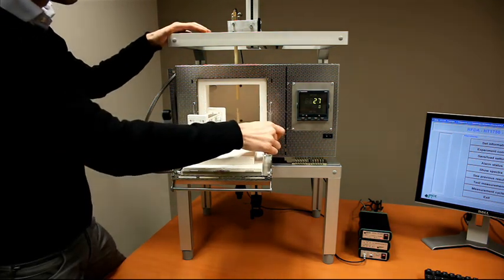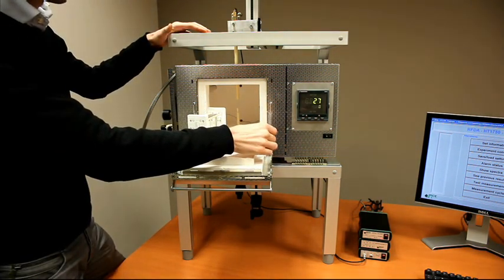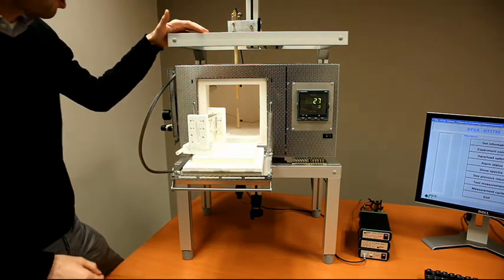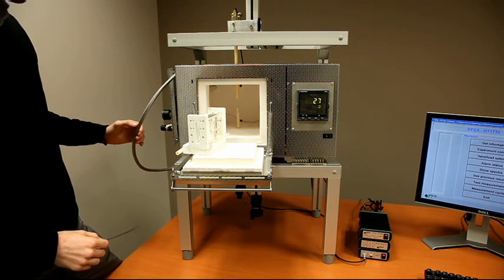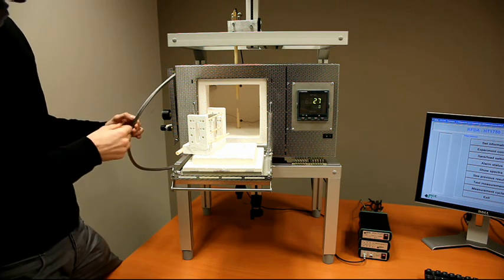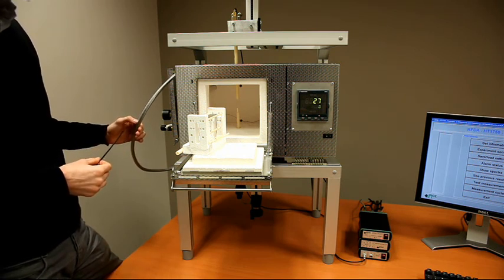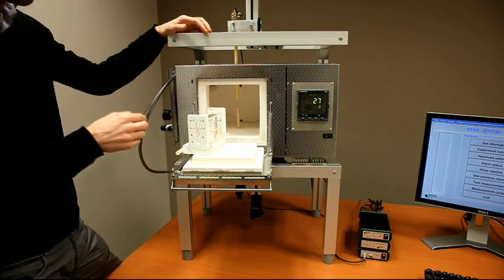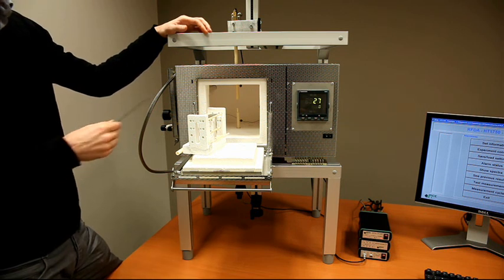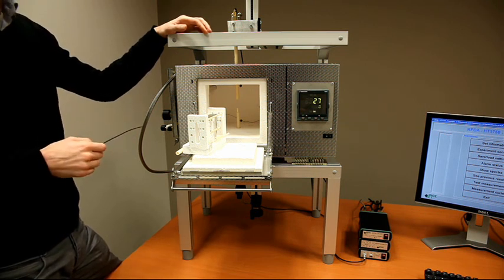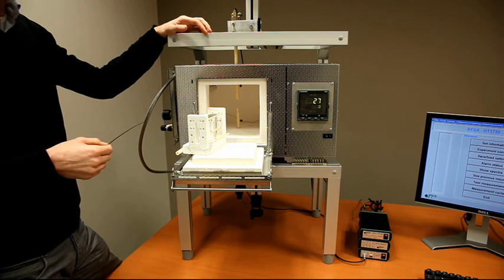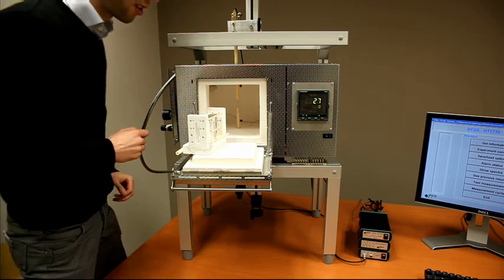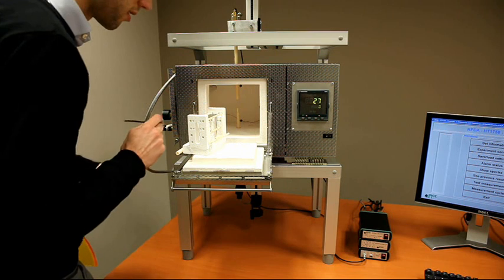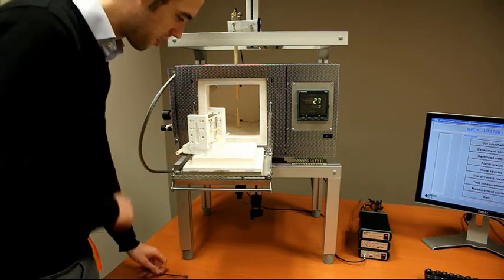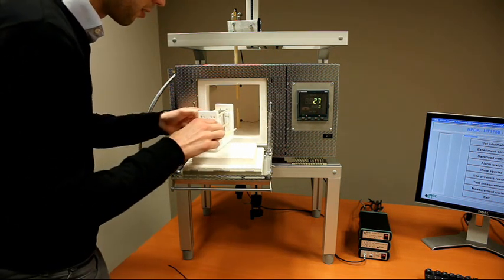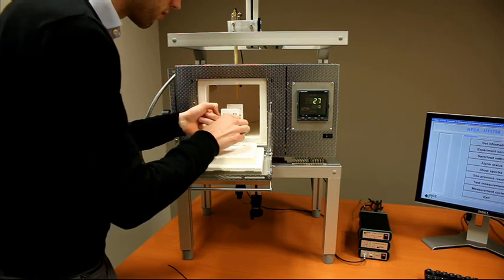On the right hand side we see the Eurotherm temperature controller, and on the left hand side we see an inert gas inflow system. So it's possible to have an inflow of inert gas inside the furnace during high temperature to slow down oxidation. Now, let's bring the measurement setup inside the furnace.